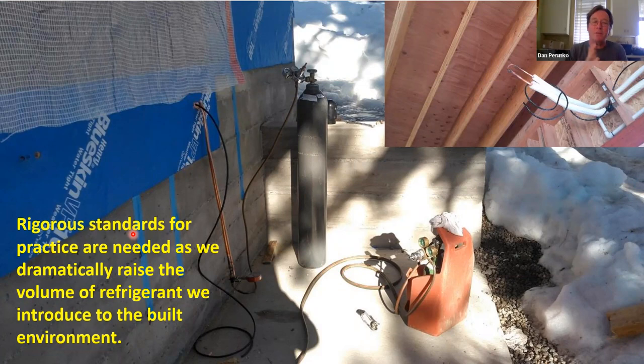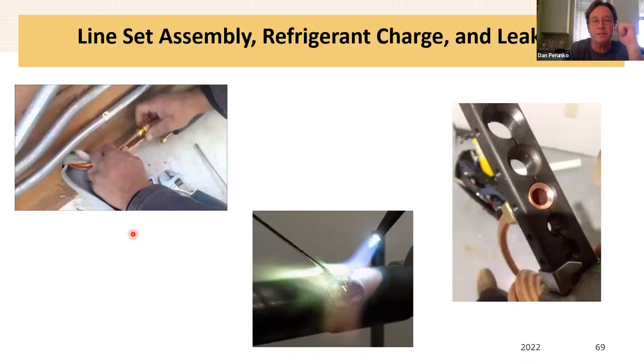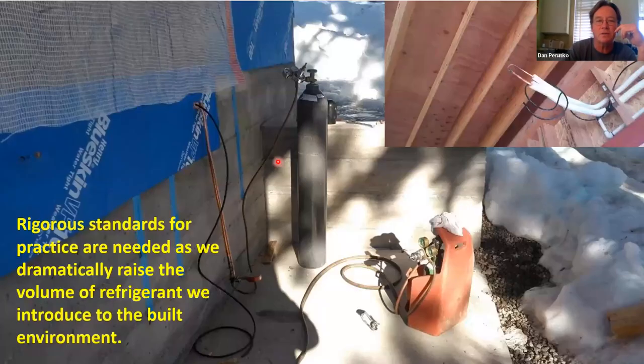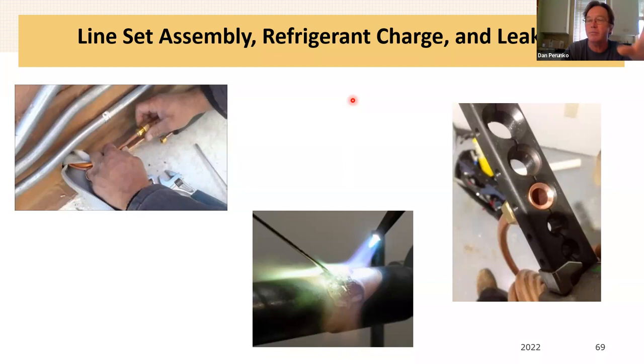Anyway, other things that we can do that improve our practices with respect to line sets is use high pressure nitrogen testing. What you're seeing here is a nitrogen tank, and this is a line set being installed, and it's being tested at 600 PSI as a pre-test. Structurally, line sets are the thing that carries refrigerant from the outside unit to the inside unit, and the mini split systems use what are called flares, and flares are a mechanical connection that's super prone to leakage.